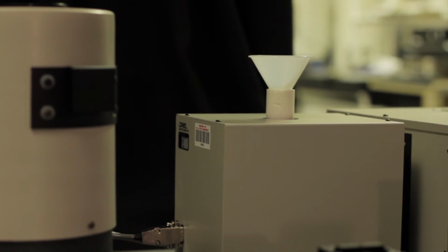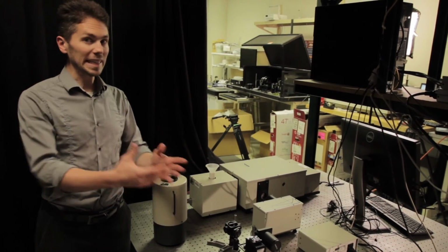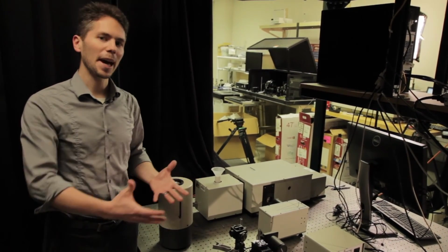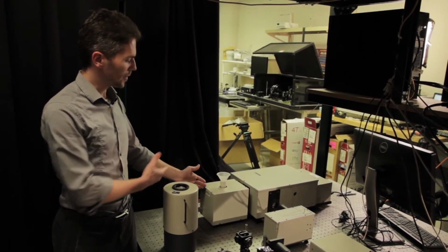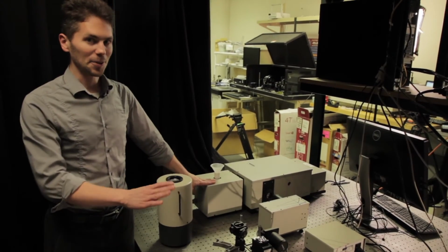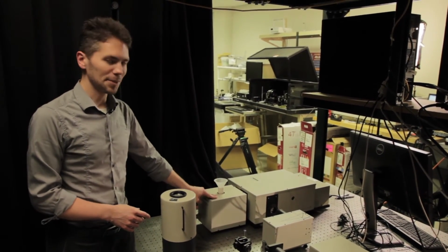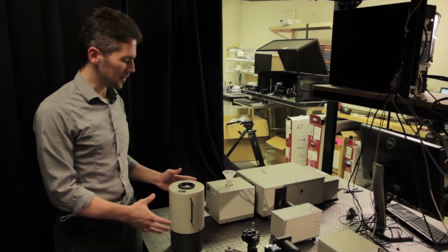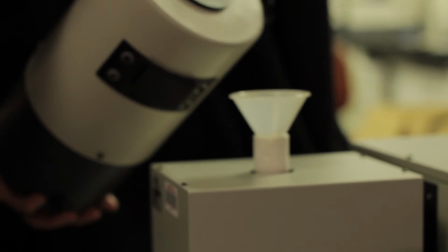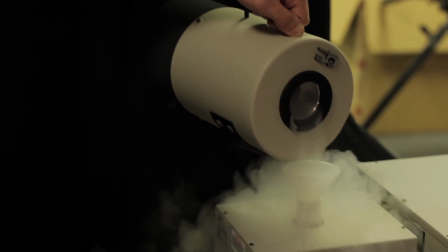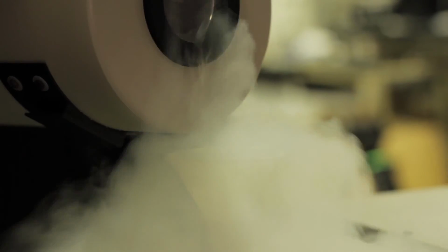Longer wavelengths of light actually correspond to heat energy. So you're actually emitting light right now in the form of heat. In a detector, when we're trying to measure light, that's a bad thing. We don't want to measure the heat coming from the detector. So in that case, we have to cool the detector down using liquid nitrogen. This is the liquid nitrogen, and we can pour it in. Once that's cooled down, we're able to measure these much lower energy photons, much lower frequency light.